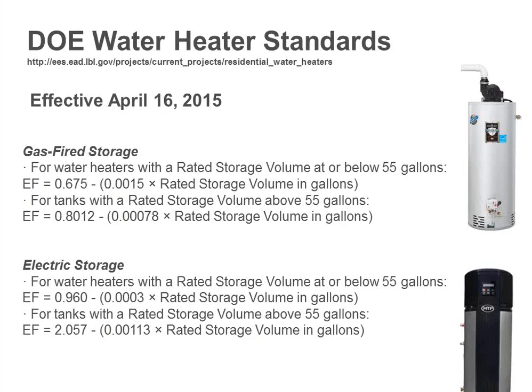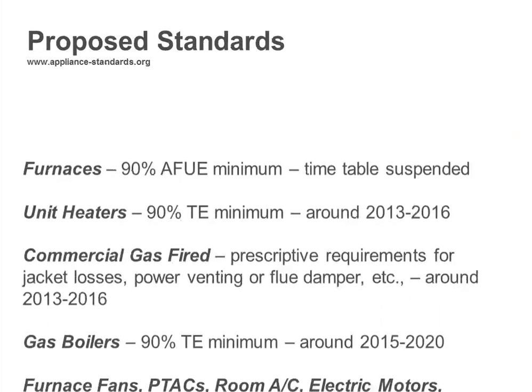On the electric side of the equation, if you have units above 55 gallons, the big change there is that the energy factor needs to be 2.057, and anything above an energy factor of 1 is going to be a heat pump water heater by definition. So if you're not familiar with heat pump water heaters, you should do so over the next year, because that's going to be coming at you pretty quickly.